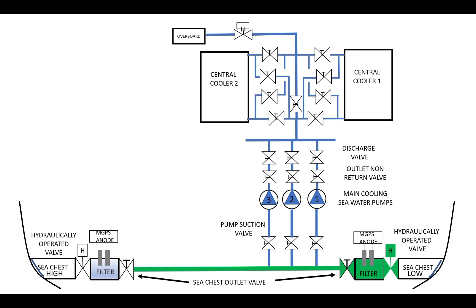Normally only one pump is in service and two other pumps are in standby in case the pump in service fails. The standby pump starts automatically if the operating pump is unable to maintain pressure for any reason. A pressure switch on the discharge side of the pumps provides the start signal.